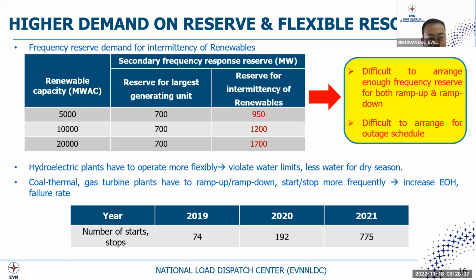The uncertainty and intermittency of renewable energy also results in impacts on frequency response reserve. With a certain amount of renewable energy that can absorb higher amounts, we have to pay attention to frequency reserve. As shown in the table, as renewable energy capacity increases, we need to increase the secondary frequency reserve, from 950 up to 1,700.